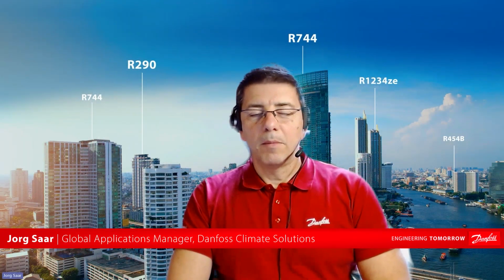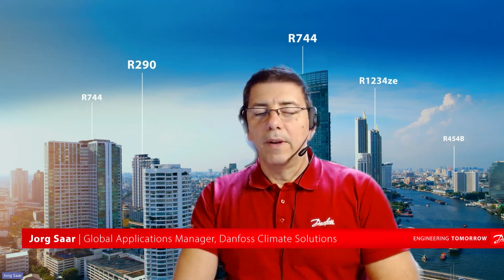Can I retrofit from a non-flammable A1 refrigerant to a flammable A2L or A3 refrigerant? Please do not retrofit from a non-flammable A1 to a flammable A2L or A3 refrigerant. That should not be done. The reason is that nobody had flammability in mind when the system was designed.